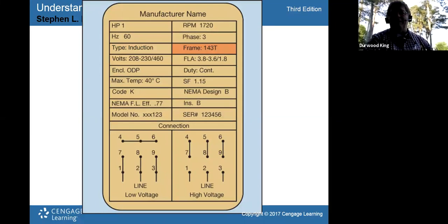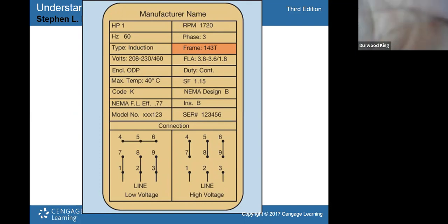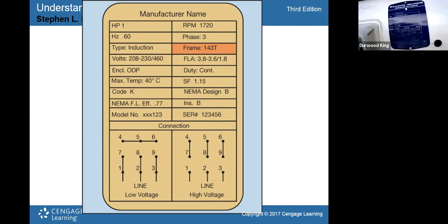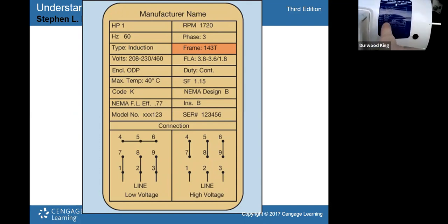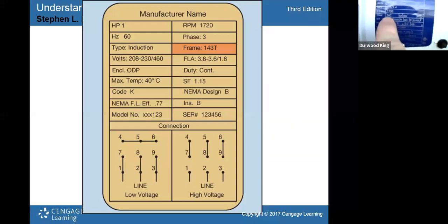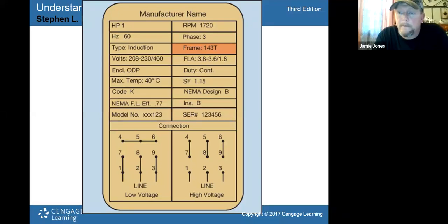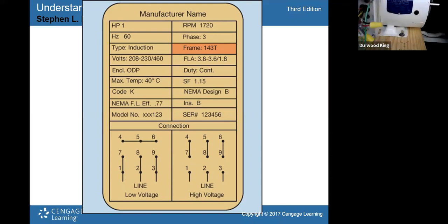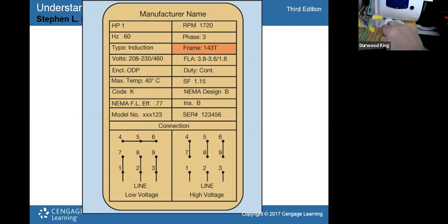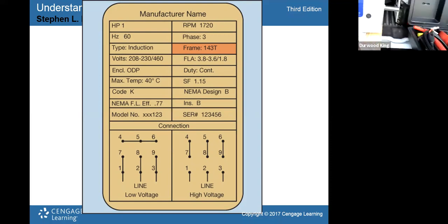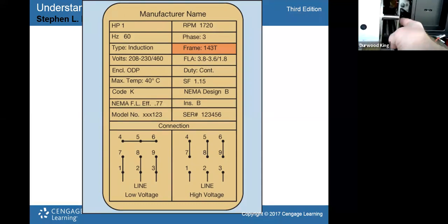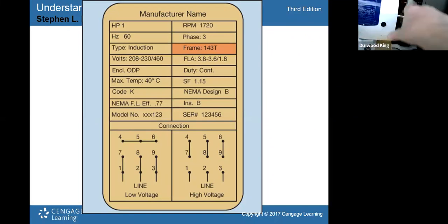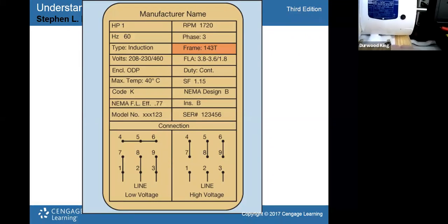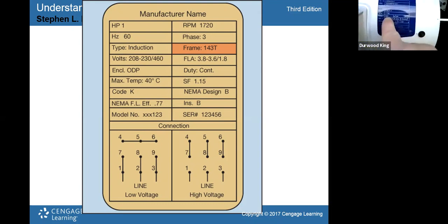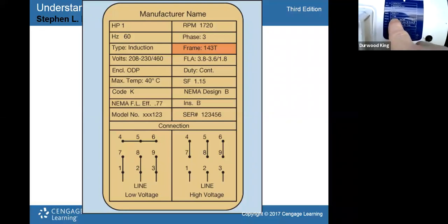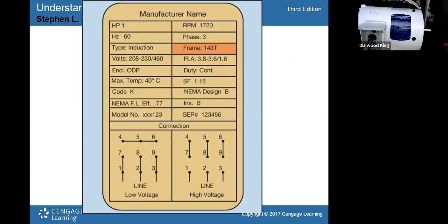The frame size, there are a lot of frame sizes. For instance, the one that I have here, this frame size says 56C. I don't know if you can read. Can you read that? Yeah, it's a 56C. So what that includes is this. That information entails the mounting type. It entails the height of the shaft from the base to the shaft. It all has to do with that. So there's a chart that we're going to look at that would take that 56C number and break it down and tell you dimensional information about that motor.